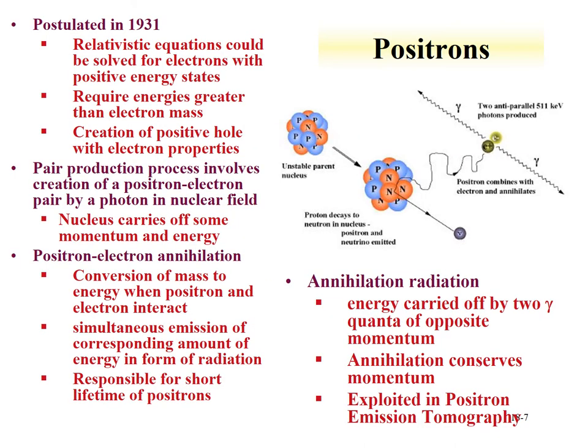An overview of positron decay is shown here. The key is a positron-electron interaction that annihilates the antimatter positron with the matter electron, creating two photons at 511 keV — each having the mass-energy of the positron and electron — emitted 180 degrees from each other. This allows a specific energy of 511 keV to be evaluated, indicative of positron decay. The 180-degree geometry means a coincidence detection system can be set up: when photons are detected in an array 180 degrees apart, working backwards gives the location where the positron decayed, enabling high-detail imaging.